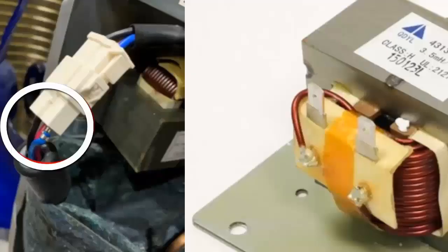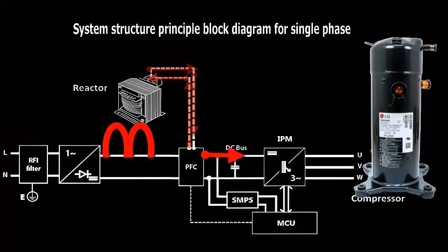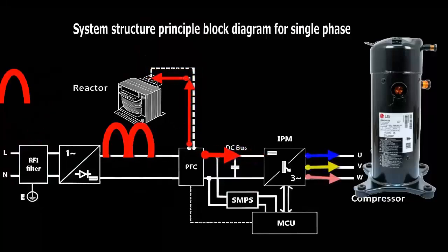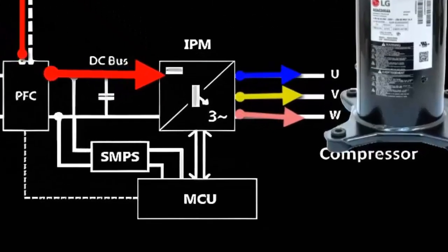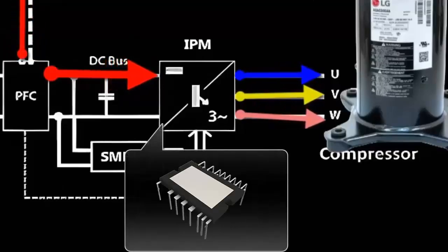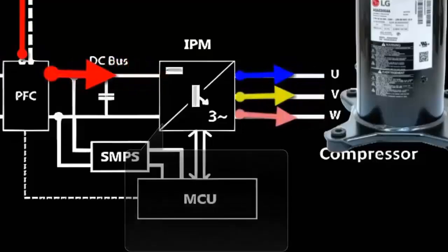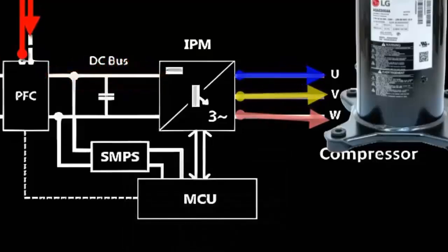Finally, to finish explaining the diagram, the stable current that comes out of the PFC circuit goes to the intelligent IPM circuit, or module, which is controlled by the main controller, and is responsible for feeding the three coils of the inverter compressor motor. In addition, the IPM electronic module is responsible for controlling the compressor speed, according to the signal from the main controller of the electronic board.